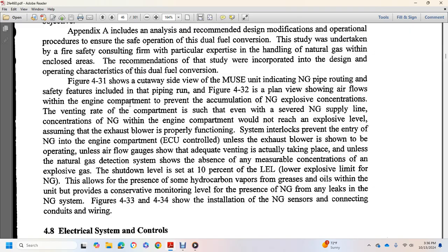Figure 4-31 shows a cutaway side view of the unit, indicating the natural gas piping routing. Safety features include the piping runs. Figure 4-32 shows a plan view of the airflows within the engine compartment to prevent accumulation of explosive concentrations of natural gas. The ventilating rate of the compartment is such that, with a severed natural gas supply line, the concentration of natural gas in the engine compartment would not reach explosive levels, assuming the exhaust blower is functioning properly.